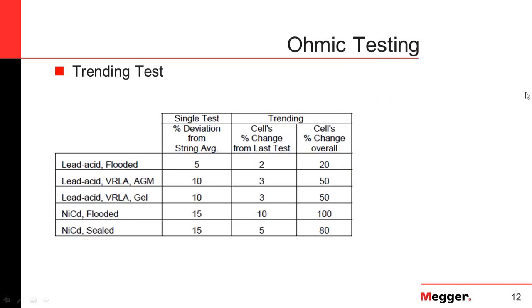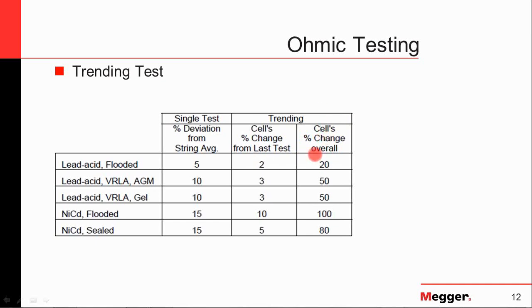The ohmic test is a trending test. You'll track averages — comparing a flooded cell against individual cells and the string average — as well as changes versus the last test date and versus the baseline. At some point I'll reach my minimum value and then it will trend upward. Tracking how much it has changed from that baseline, which might have been five, six, or ten years ago, is key to understanding battery health.